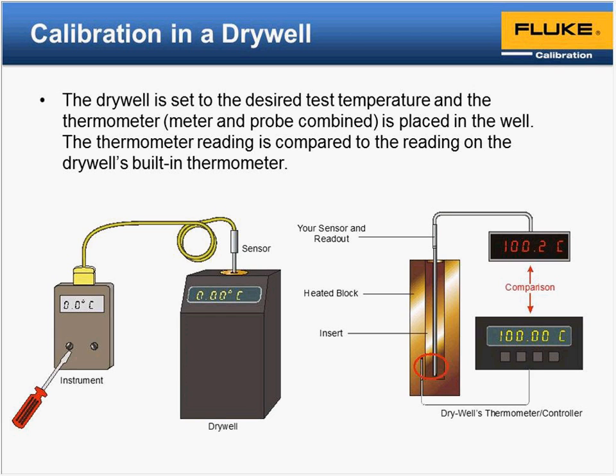So in this case, you can see our setup. We're going to now leave the thermometer and probe connected and then place them in the well. If you see the picture on the far right, in a dry well, you have the probes fully immersed. The idea with any dry well application is to place the probe that you're testing as close as you can, which is usually full immersion in the dry well that you're using as the source. The reason for this is if you had a very short probe, say a couple of inches, and your probe did not go all the way down to the bottom, you can experience a pretty significant gradient error that you do not account for. So again, things to consider there.